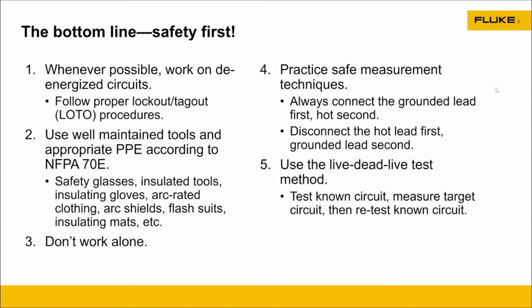And then follow those safe measuring practices. Make sure your techniques are right. One of the great techniques that I've learned through time is that typically when you're doing a voltage check with your DMM, you always want to put the black lead on first, and then go to your ground possibly, and then go use your red one to hot. And then when you're done making your voltage measurement, you pull off your red, then you pull off your black. And that could work even with split phase or three phase or whatever you're looking at. But if you always just know that you go black on, red off, black off, it's just good practice. And then always do that live dead live test. That's always a key one.